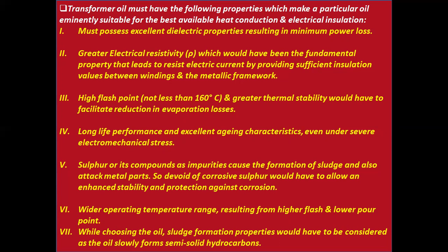Number two, greater electrical resistivity, which is the fundamental property that resists electric current by providing sufficient insulation values between windings and the metallic framework. High flash point, not less than 160 degrees centigrade, and greater thermal stability to facilitate reduction in evaporation losses. Long life performance and excellent aging characteristics even under severe electromechanical stresses.